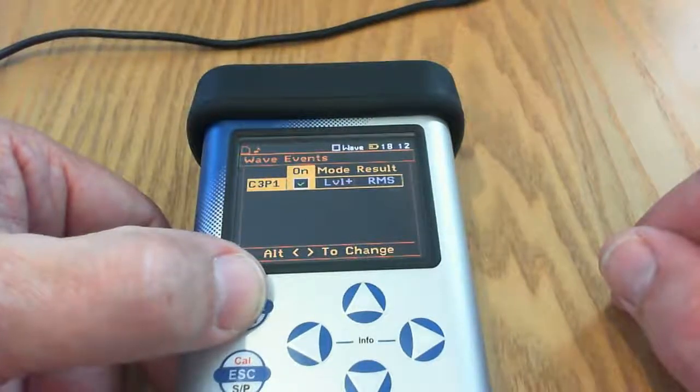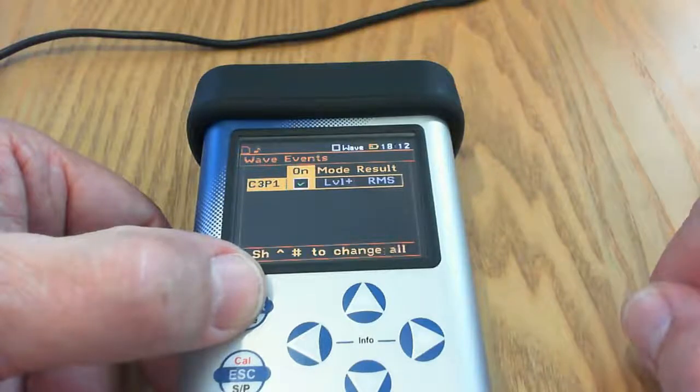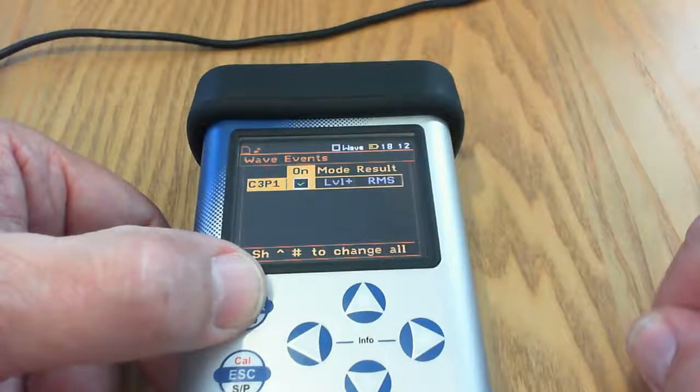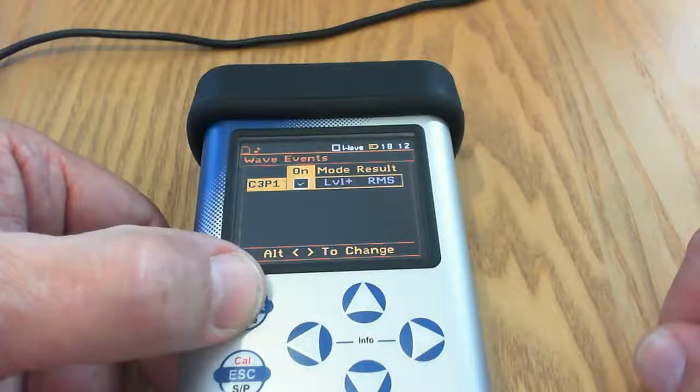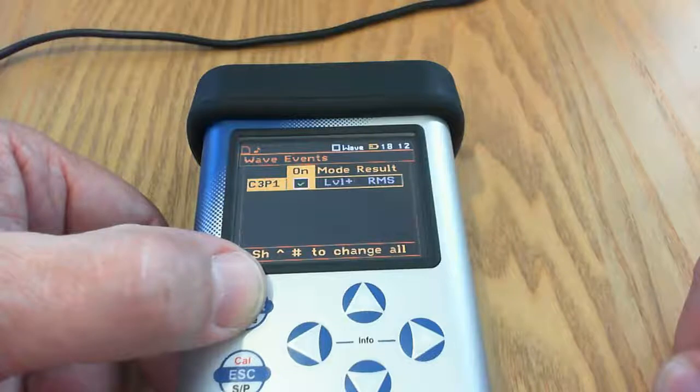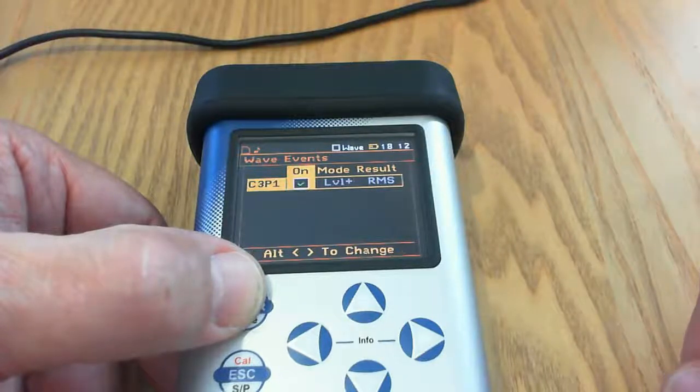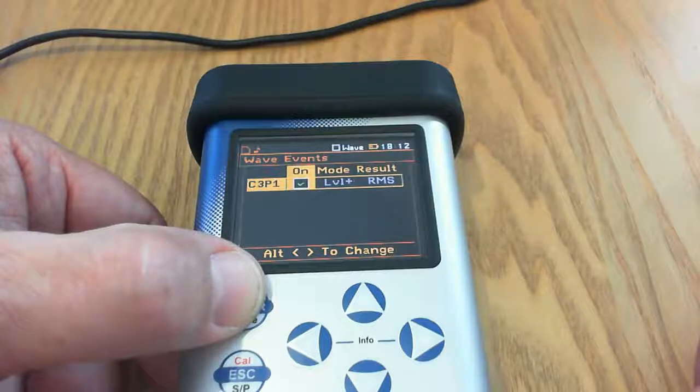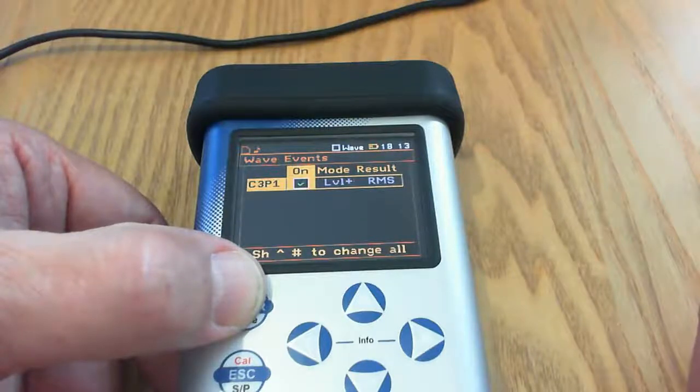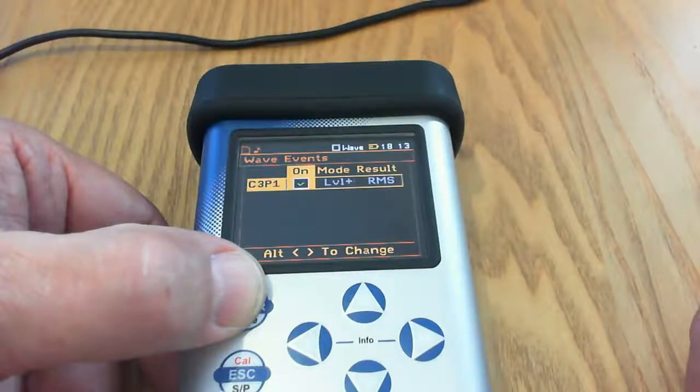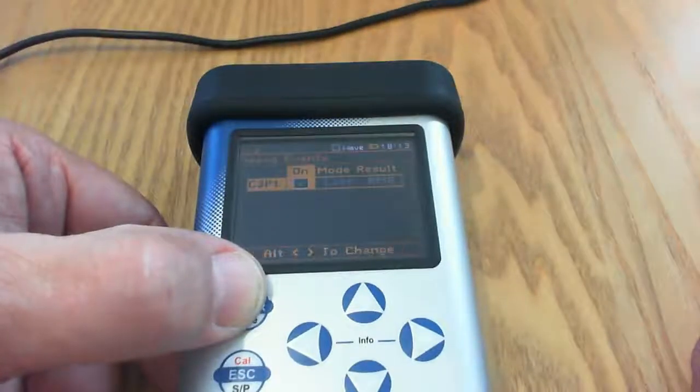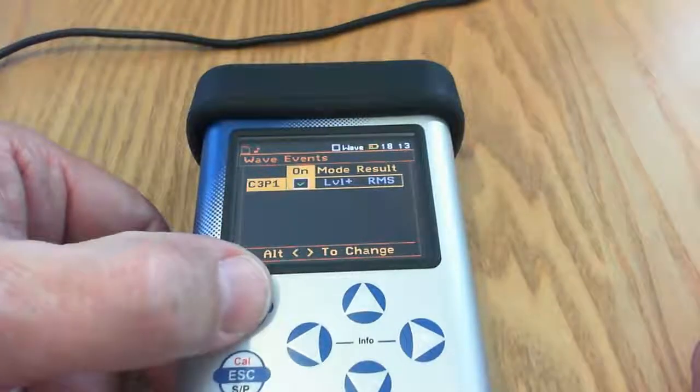Now we need to select the source of that trigger. Here you can see the trigger event that I defined in the other menu. You can see at the moment it's set to channel 3, profile 1. It's active, it's switched on, and the mode is the level going above a certain threshold and it's going to trigger off the RMS result. So that's it. Obviously you can see that you can put in some other triggers here as well to trigger the wave. You can make some quite complicated profiles. So that's it. We're all ready to go.